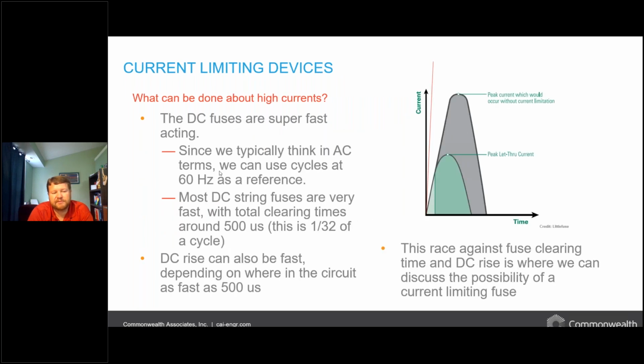So again, just another example of what we're talking about with these current limiting fuses is that we're really looking at this race. How steep that curve is, how fast the fault current rises, is really what we're tracking. You can see with the red line that I imposed on this graph that DC systems can be much, much faster than AC systems. If that DC rise is fast enough, it may rise before the current limiting fuse can operate. In our last example, we were coming in somewhere around 0.8 milliseconds, but we've seen applications that are much faster than that.